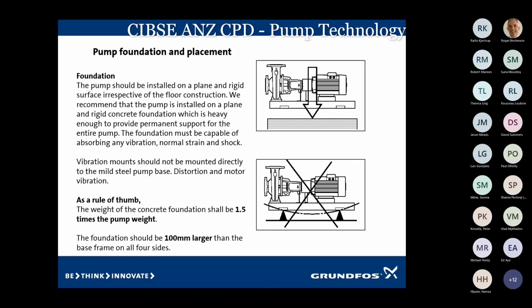One other point while I'm thinking about it: when you're starting up a pump, commissioning that pump, always get the discharge valve and close it off. So when you start that pump, just open the valve slightly and hold it there. You're holding the pump high up on the pump curve. When the system is filling and it's balanced, then gradually open up the valve.